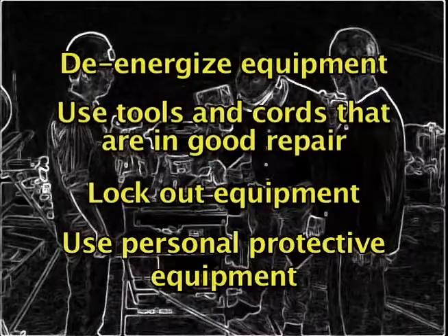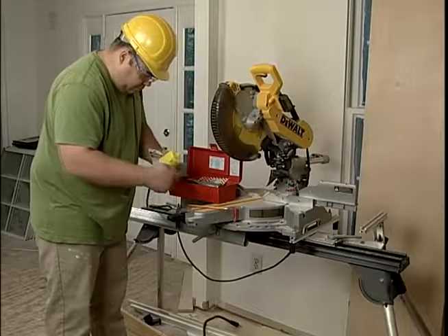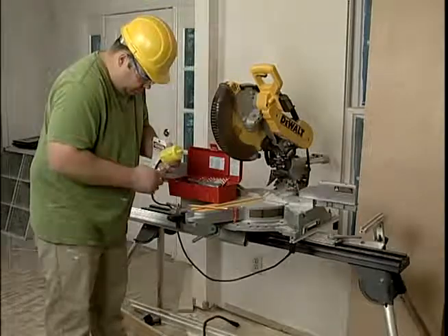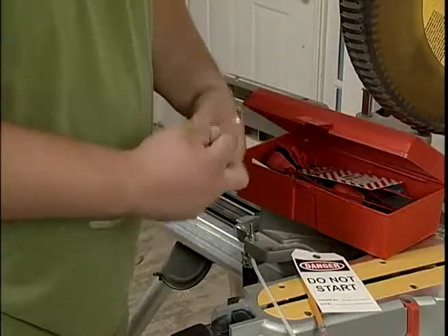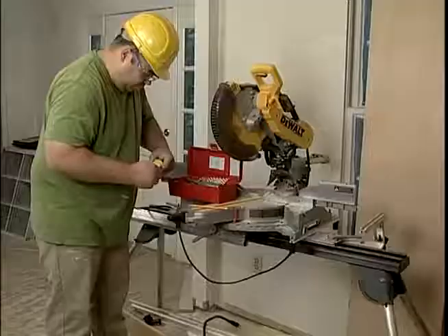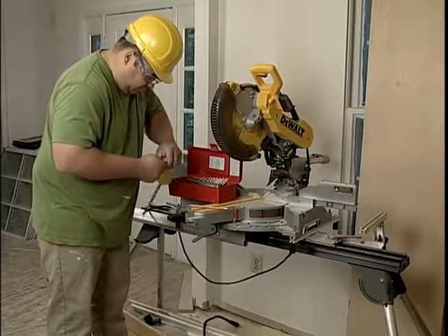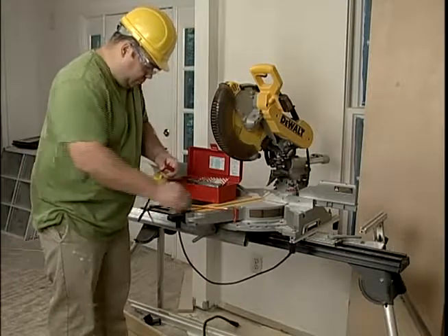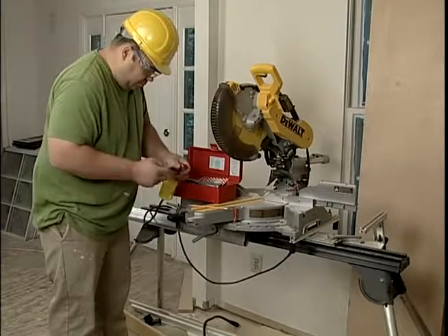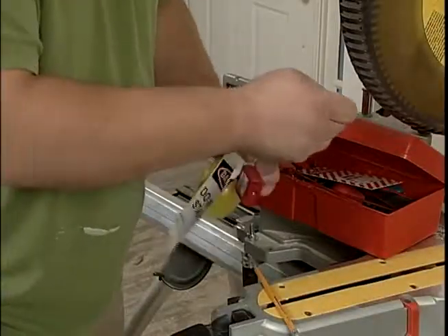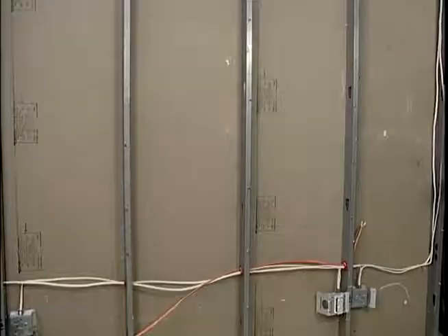working with electricity. Employers must also make sure that all workers on the job site know how to use proper lockout-tagout procedures, including which controls need to be deactivated while equipment is being worked on, which de-energized equipment or circuits need to be locked out and tagged, and where locks and tags should be placed. That tags must plainly identify the equipment or circuits that are being worked on.